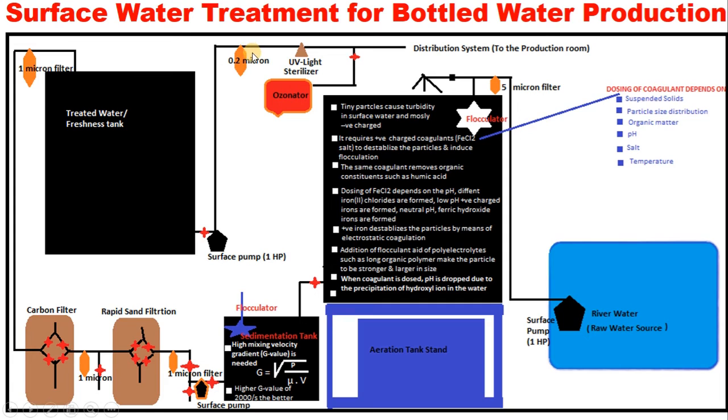Once water passes through it, it will come into the UV light sterilizer. UV light sterilizes the water in case there is any microbial growth or any pathogen along this line. UV light will handle it, and in most cases we suggest UV light of about 200 to 225 nanometer range. It is safer, it disinfects fast, and the efficiency is very, very high.